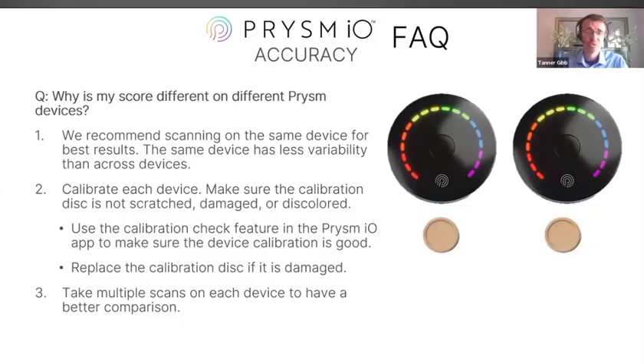However, number two, we would recommend calibrating each device. Make sure the calibration disc is not scratched, damaged, or discolored. Use the calibration check feature in the PRYSM IO app to make sure the device calibration is good. Replace the calibration disc if it is damaged. And when in doubt, just recalibrate the device. Make sure that it's calibrated on a frequent, regular basis for best results.